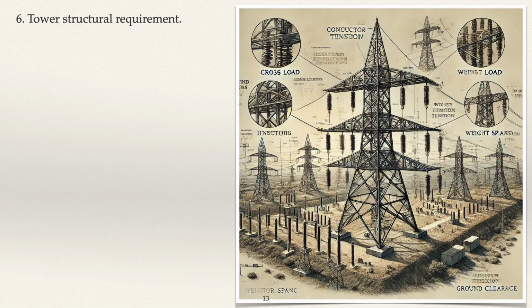Towers' weight must support the combined weight of conductors, insulators, and fittings under normal and extreme conditions like wind and ice loading. Includes additional allowances for dynamic forces like conductor tension and vibration. The tower materials are commonly galvanized steel to provide durability, strength, and corrosion resistance. Alternative materials like aluminum or composite materials may be used for specific conditions. Design standards must comply with national and international standards like IEC for structural integrity and performance.